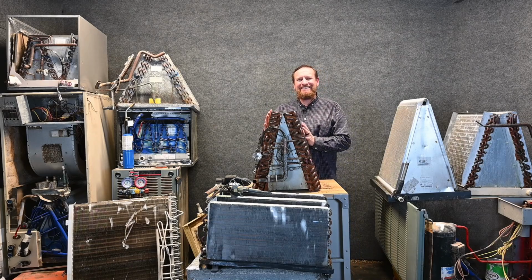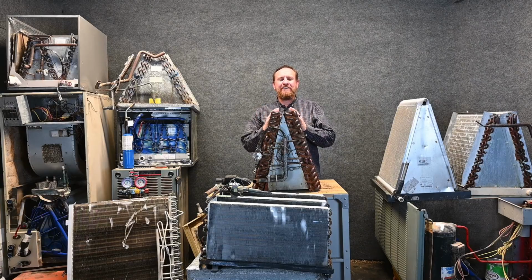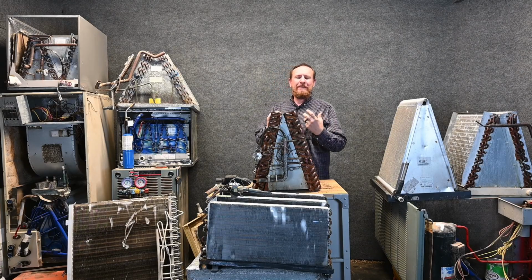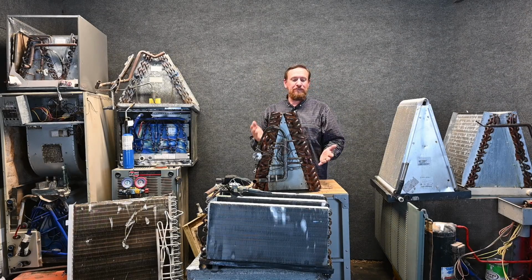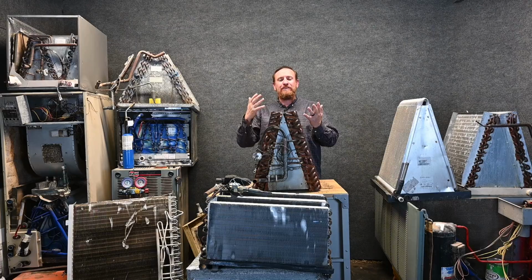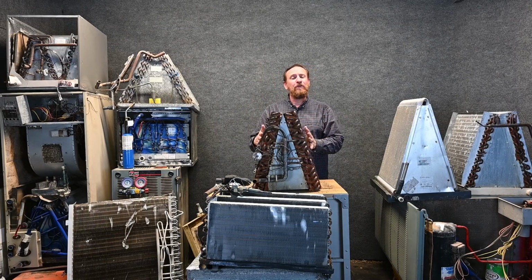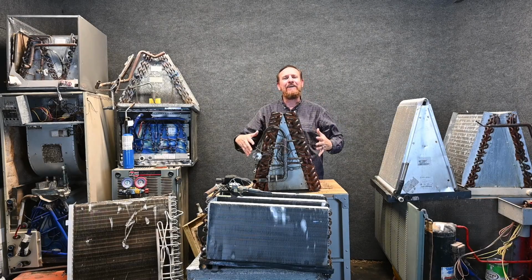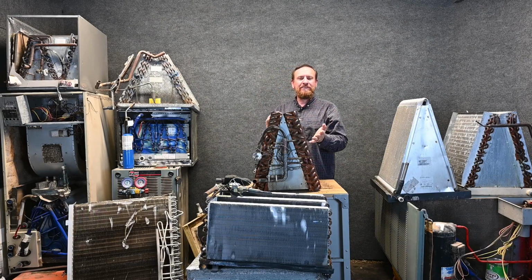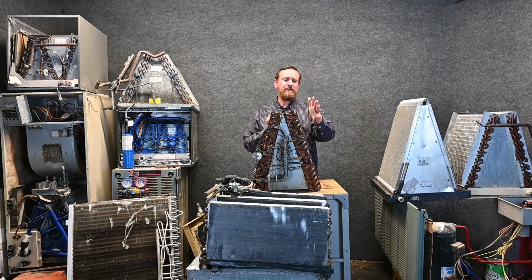Now we talked about leaks in the evaporator coil. You have to clarify, especially with the customer, what kind of leak it is. So typically in HVAC, when we talk about leaks, we're talking about refrigerant leaking out. So refrigerant leaking out is definitely a big issue. We have to find the leak, and a lot of times in these evaporator coils, we can't fix the leak. We end up having to replace this entire component right here because the risk is too high. You spend all the money charging the customer to fix this leak, and then it doesn't work. They expect you to keep coming out and fixing it forever.